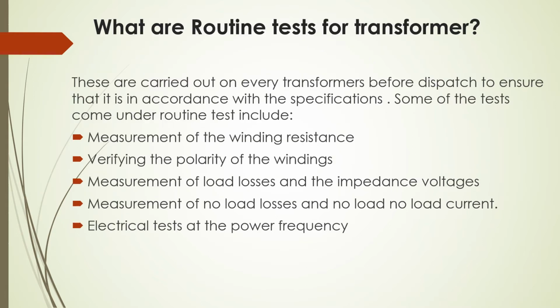What are the routine tests for the transformer? These are carried out on every transformer before dispatch to ensure that it is in accordance with the specification. Some of the tests that come under the routine tests are measurement of the winding resistance, verifying the polarity of winding, measurement of load losses and impedance voltages, measurement of no load losses and no load current, and electrical tests at power frequency.